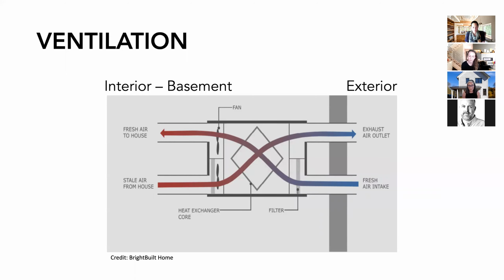Inside the unit, the diamond shape is the core. It's a heat exchanger. And you can see the airflow through the exchanger. The gray bar to the right of that unit is the exterior wall of the home. And so the unit is placed on the exterior wall. Well, there's an inlet and an outlet on the outside of the home. One is bringing fresh air into the home, passing over the heat exchanger, and that is supplying our living rooms and bedrooms. Alternately, air from bathrooms and kitchen are being extracted, goes over the heat exchanger, and exhausted to the outside of the home.